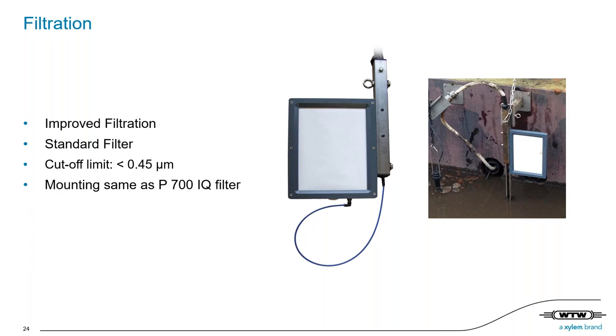A well-working, easy-to-maintain filtration is of course essential for reliable measurement. Thus, we also improved our passive filter for the Alyza units. The filter material itself is more robust, and the material between the 2 filters is more rigid, making it easier to periodically clean. In addition, it has a larger surface area, so it will require less frequent cleaning. So the filter expected life is greater than 1 year. We have even installed filters for over 2 to 3 and more years. The material of the housing is PVC and the membrane is just polyethylene, which is very stable and simple to maintain.